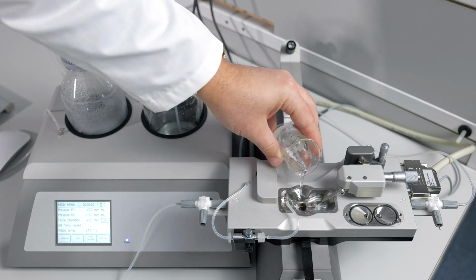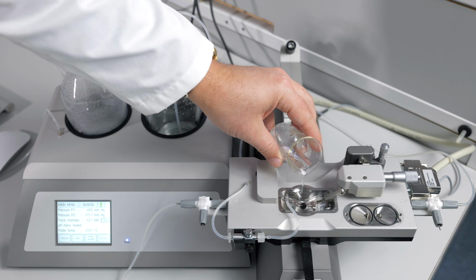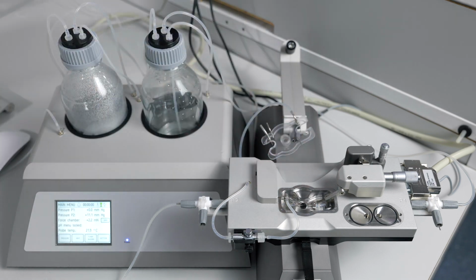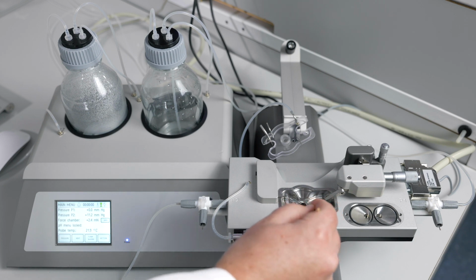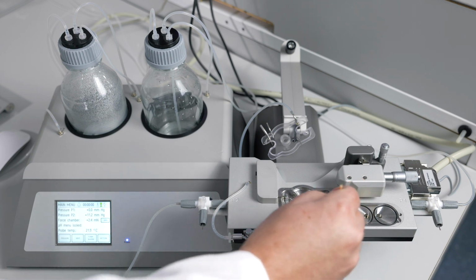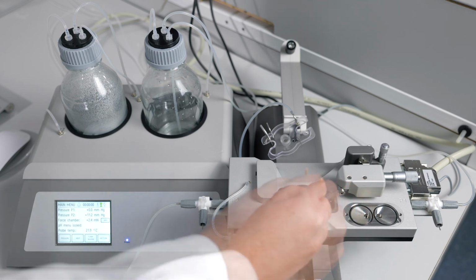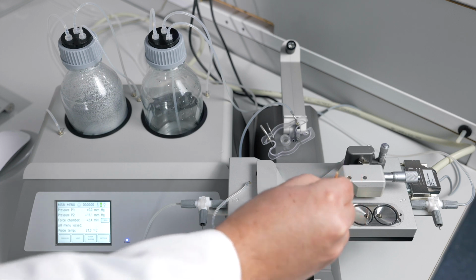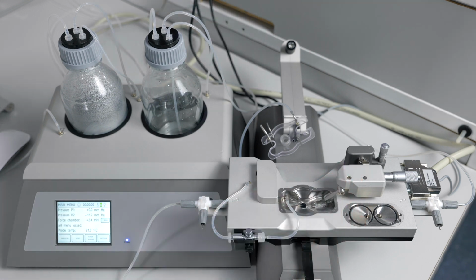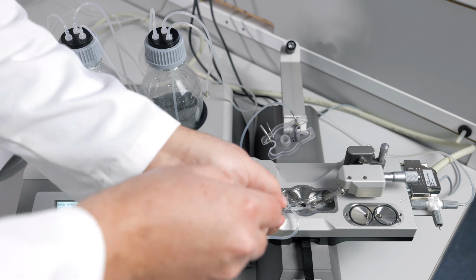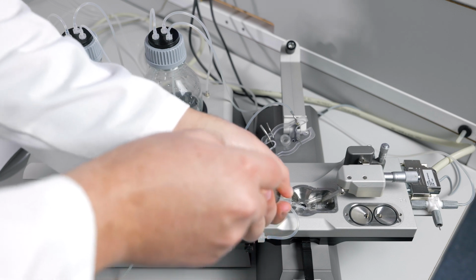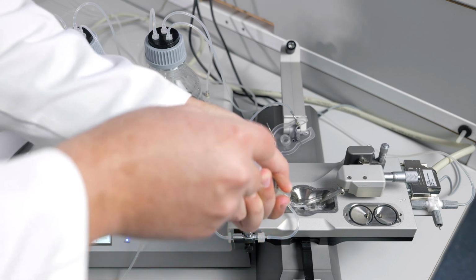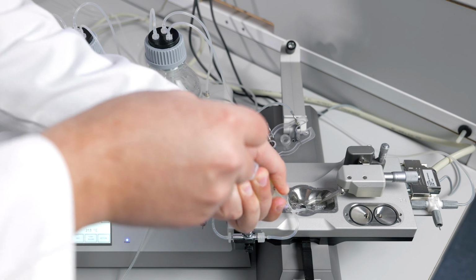you will fill the chamber to the top and let it soak for 1 to 2 minutes. You can also use a swab stick to rub down any place that you saw the salt buildup. Be careful to avoid hitting the force transducer mount. Once this is done, you need to remove the acetic acid and do at least 3 distilled water washes.